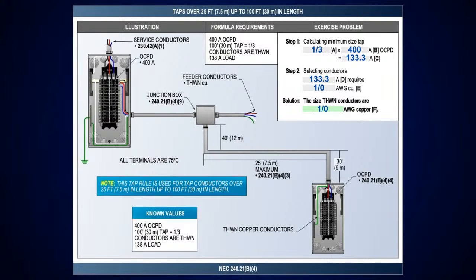Sure, and it is true, and that's why we bring this stuff up. And this one here, this is a 100-foot tap, and you'll notice we also put some rules in there for how that would be installed. 30 foot up above, or panel board and all this other stuff, and then 25 foot maximum. So we put all that stuff there if you want to reference it. But in this case, we've got a 400 amp upstream. Take it at a third. Everything that's left, at a third. That gives you 133.3. And in this case, we're doing copper.